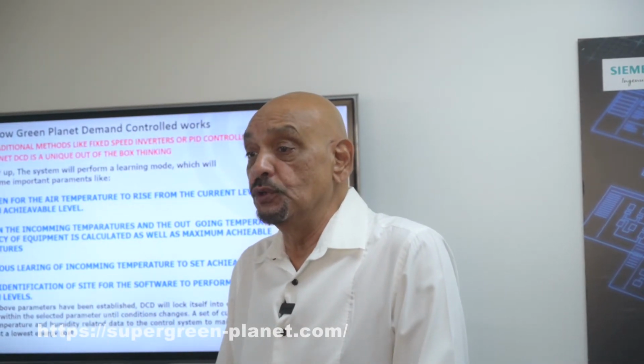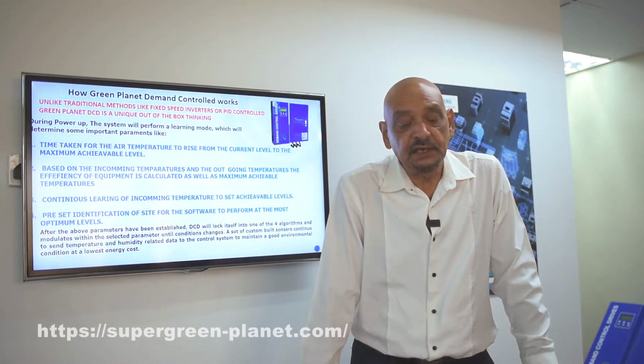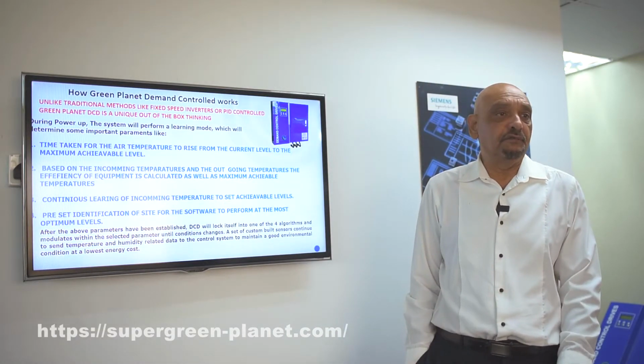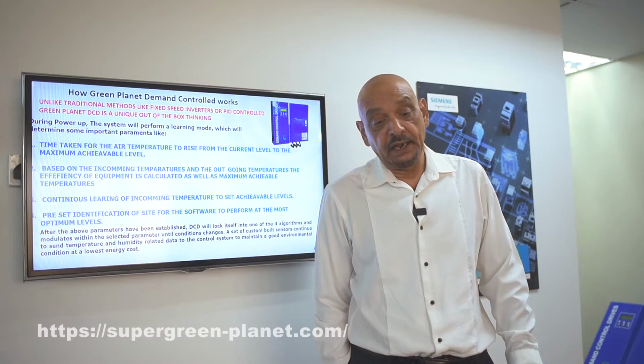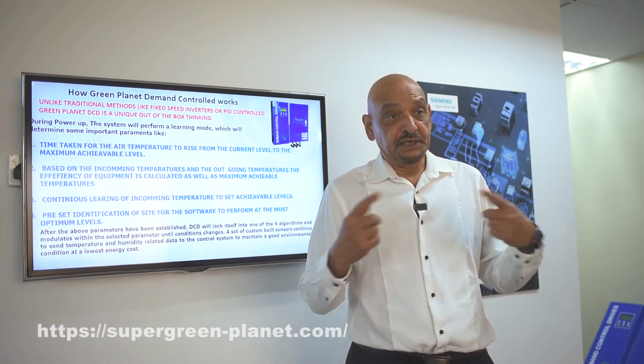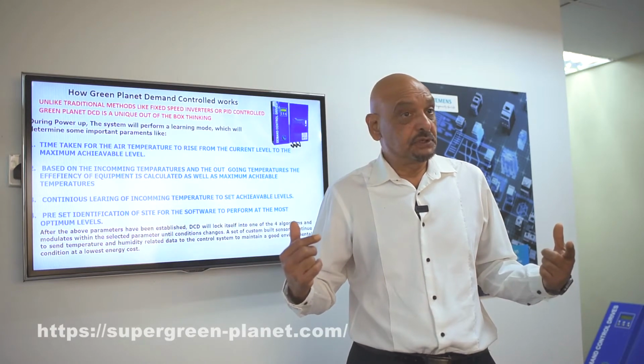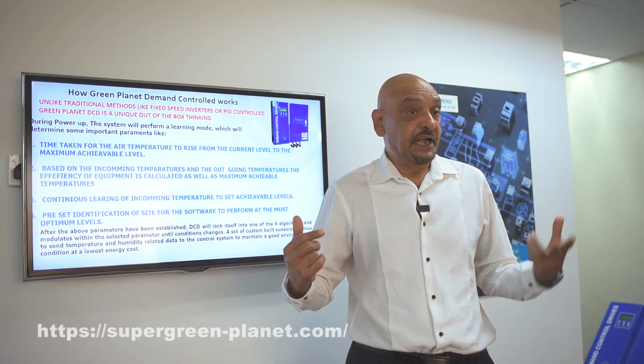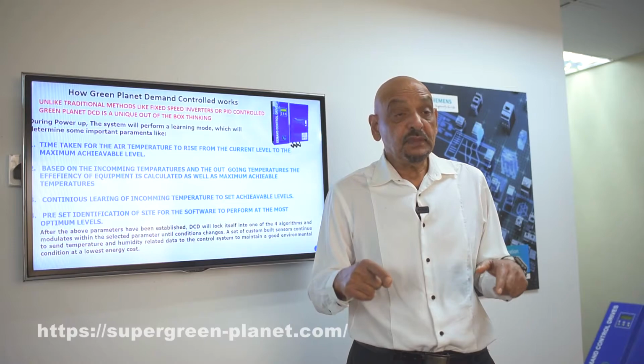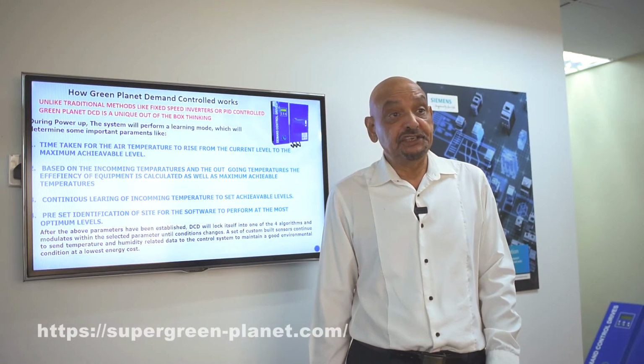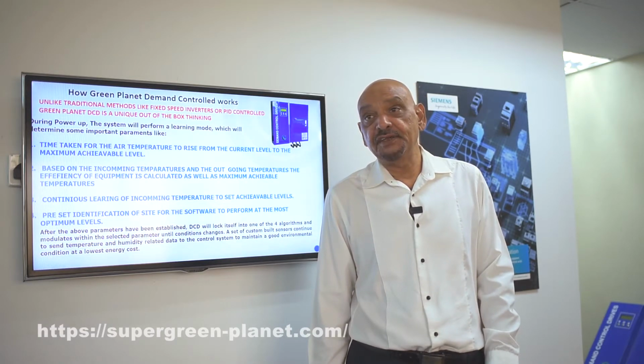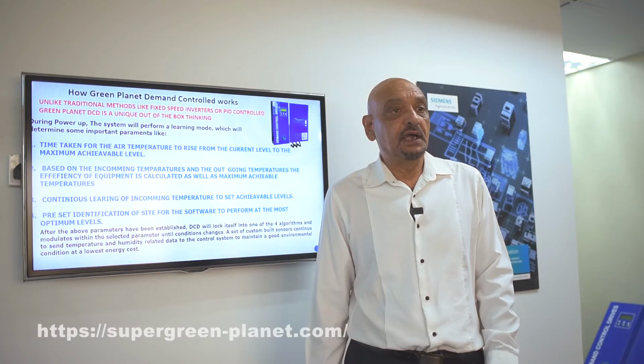Now, how does the system log into one particular algorithm? The first thing the system will do is remove air turbulence. In a standard star delta autotrans configuration, your air handling unit would run to an extent where the intake becomes a low pressure zone and the exit becomes a high pressure zone. What happens here is you have a lot of air turbulence within your air handling unit, and this is where a lot of your noise comes from. That is one fact. And the second fact is that it reduces your air handling efficiency.